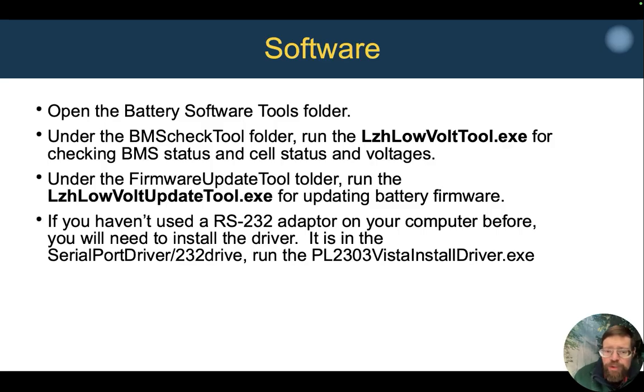There's 2 different programs in there. Under the BMS check tool folder, you'll see lowvolttool.exe, which is the program to run for checking the BMS status and cell voltages. There's another folder called firmware update tool, with lowvoltupdatetool.exe, which is the program for updating battery firmware. There's also a folder called 232 drive, which is the driver for the RS-232 adapter.